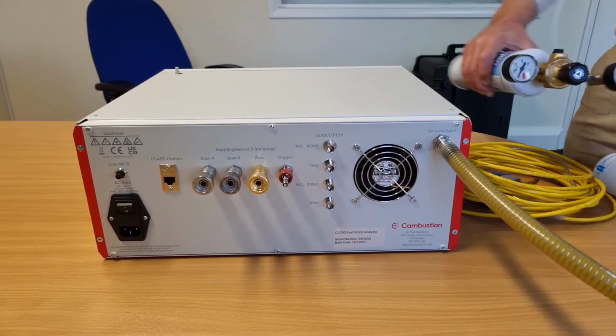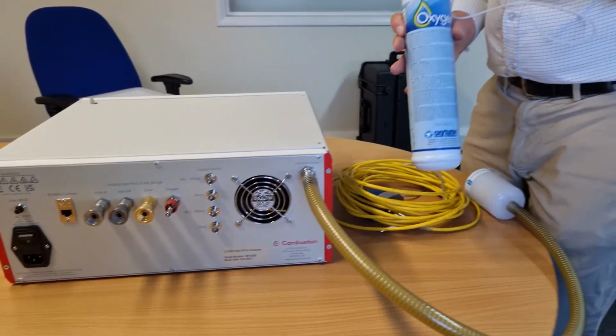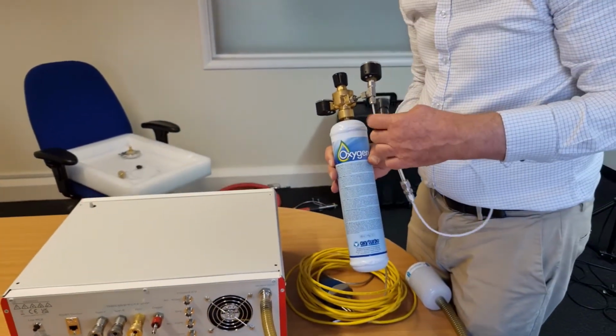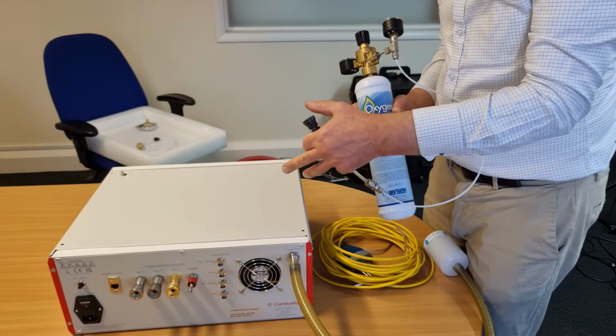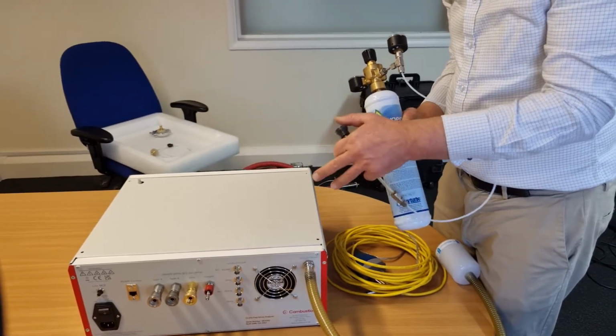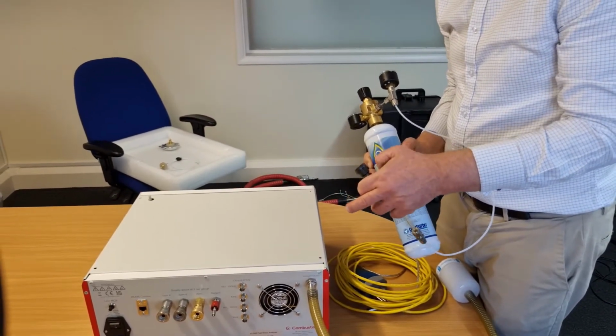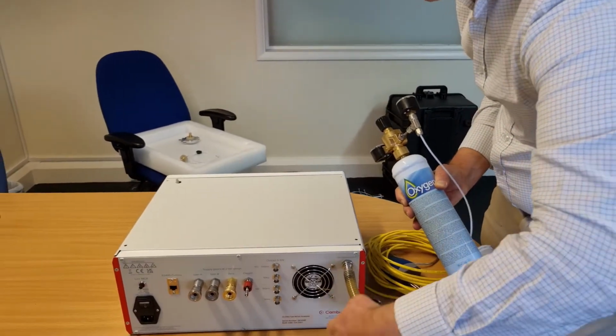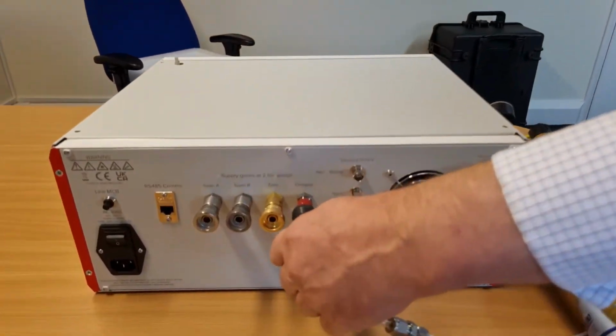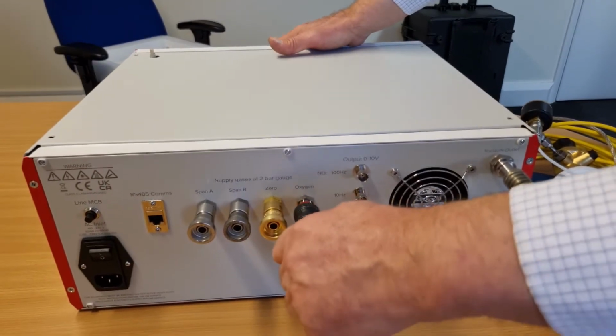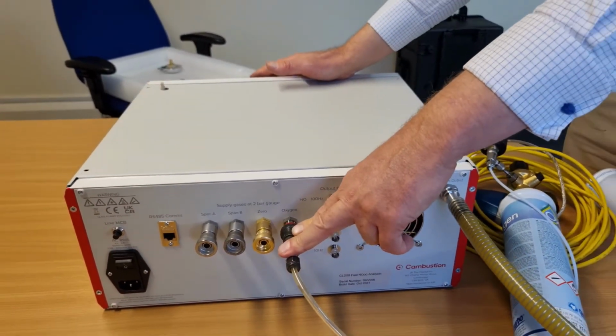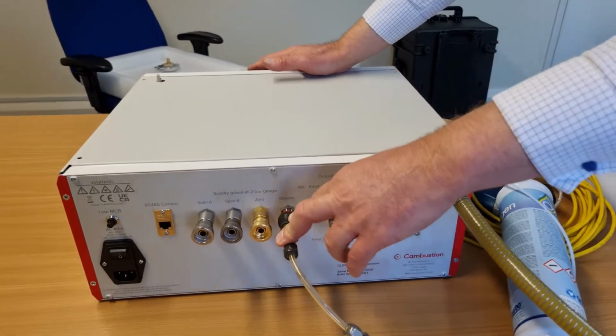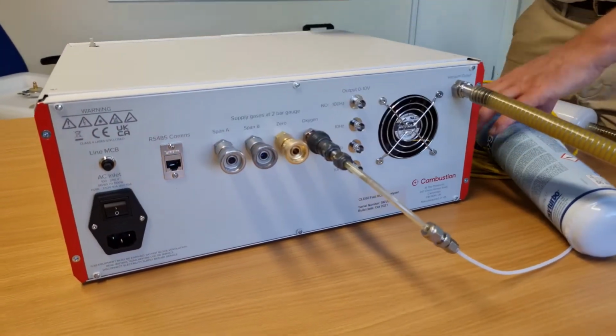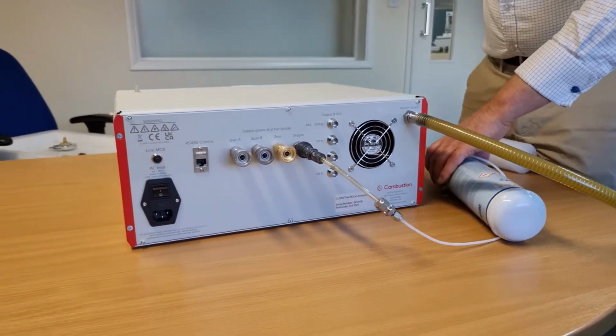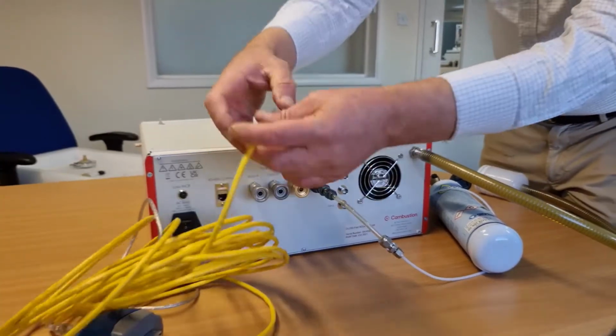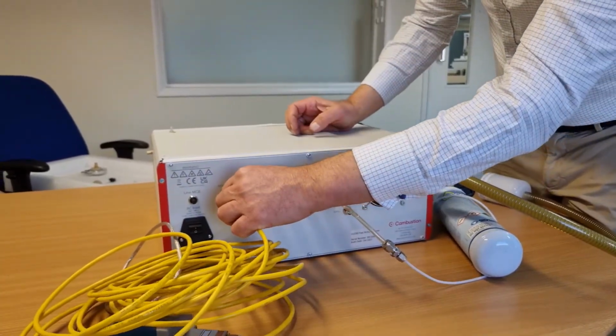I'm using this small portable bottle of oxygen, and something of this size will fuel the CLD and LIF system for about 2 working days. But the connector, which is a shut-off gas connector, plugs in here, and we supply the oxygen at a pressure of 1 to 2 bar gauge. This is where your span gases go in. And our RS485 signal cable, this is what we're controlling the analyzer with, it'll plug in.